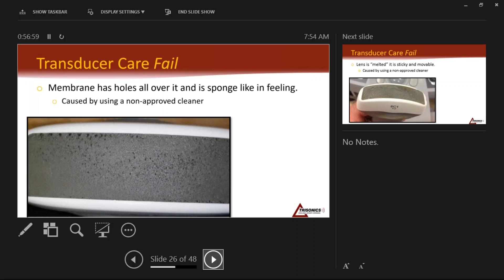For most of the major manufacturers, Siemens, GE, Philips, they have really good web pages now for disinfecting and approved cleaners, that kind of thing. You can go there, put in your probe types, and find what cleaners are approved for each probe. It's also very important you do each probe, because sometimes a manufacturer will not approve all the same cleaners for one particular probe as they do for all the other probes. So it's always good to check. Matter of fact, this next example, by the way, those holes, that lens on that ultrasound transducer was like a sponge. That's what it did, it turned it into that.